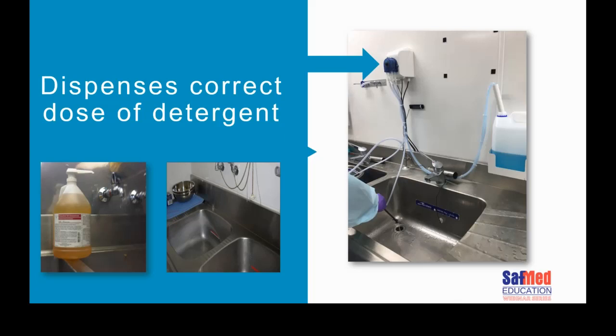In the South African setting, we often use a pump. Please be cautious that you're using the correct pump, or the pump that came with that particular manufacturer's detergent, because they don't necessarily all dose the correct or the same amount. If you use too much detergent, aside from wasting money, will it rinse off correctly? If you use too little detergent, will you clean effectively? It's a very simplistic point, but a very important point to get cleaning efficacy.